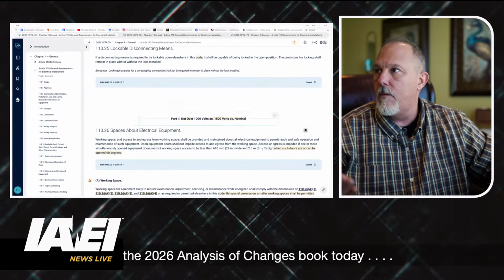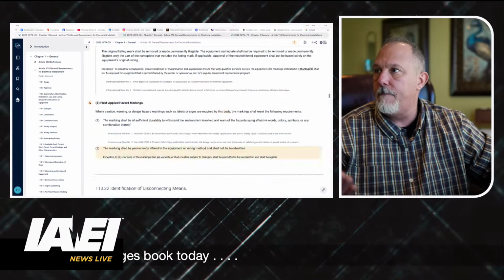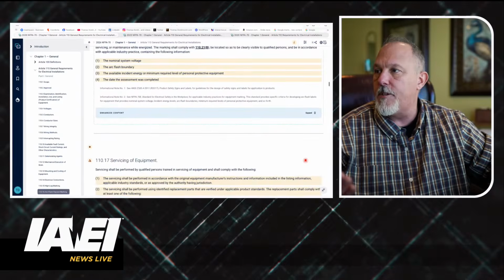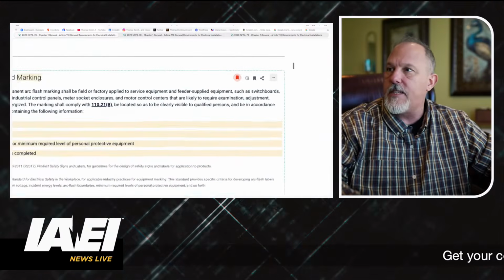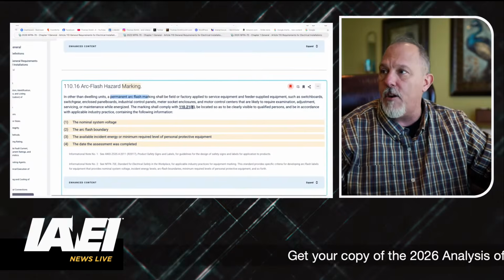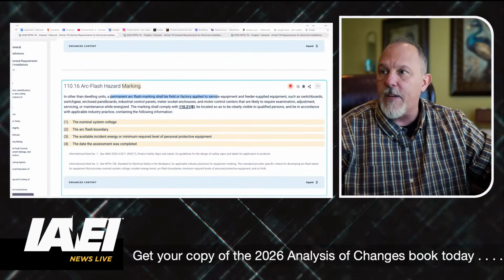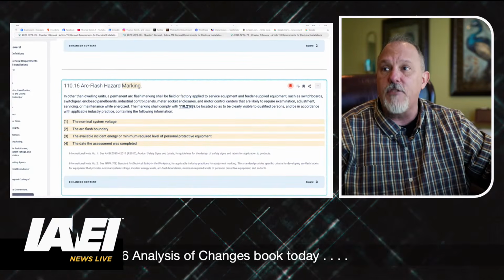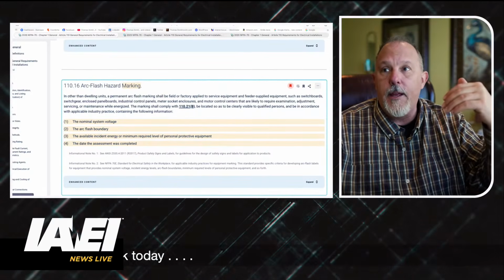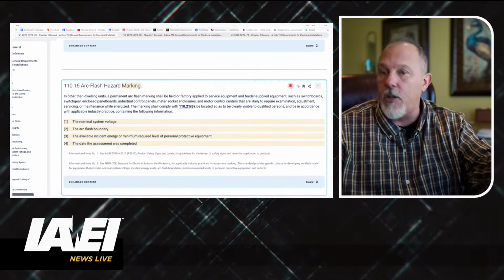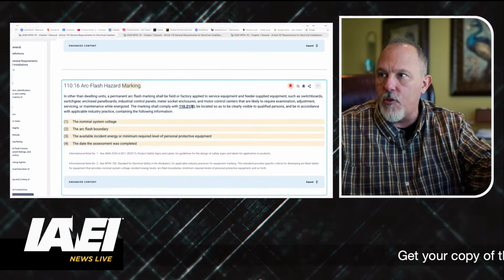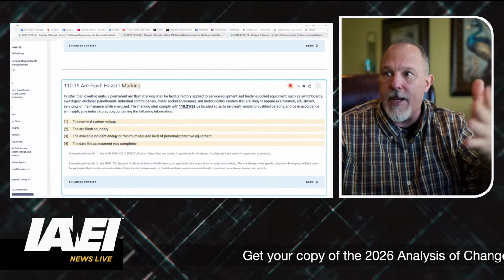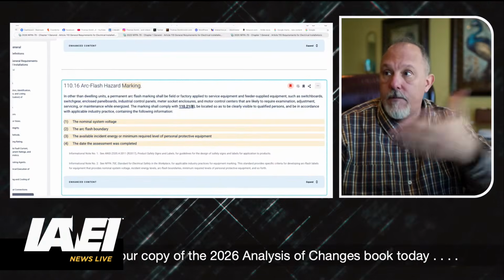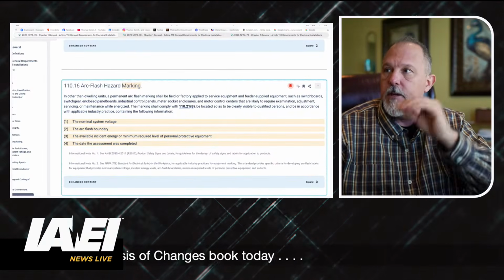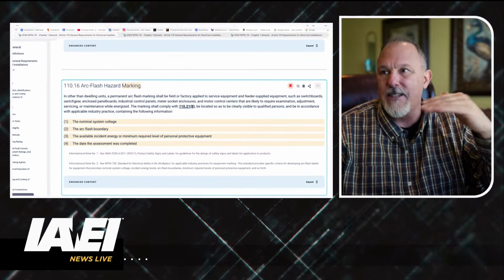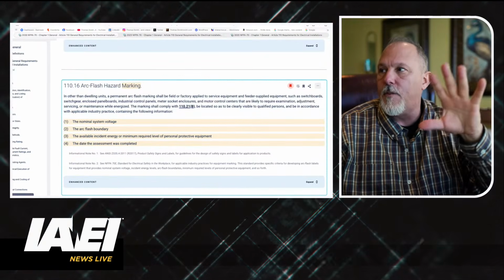And 110.16, where's it at? Let me just pull up the language. It'll be easier. All right, so what we said was you need a permanent arc flash marking shall be field or factory applied to service equipment and feeder supplied equipment. So it says such as switchboard, switchgear, enclosed panelboards, industrial control panels, but 'such as' really expands it. I mean, I could have a disconnect switch if it's feeder supplied. There's no limitations, which is a challenge with this. It does say other than dwelling units.